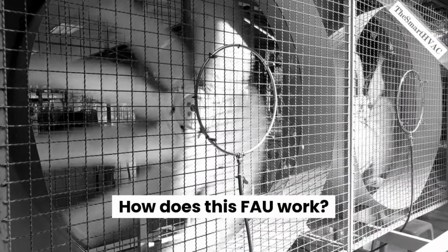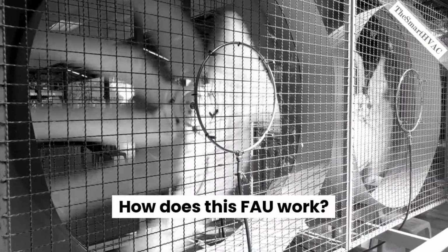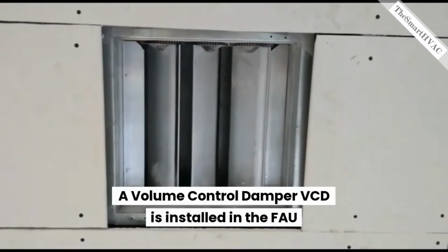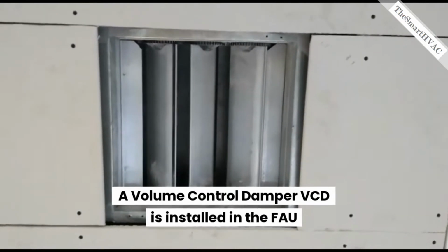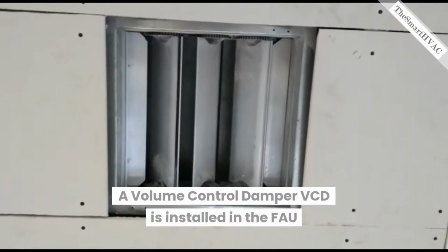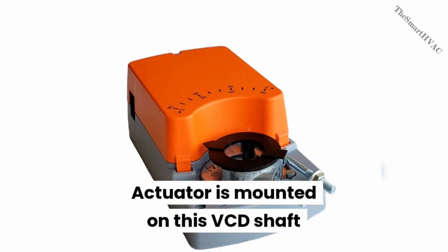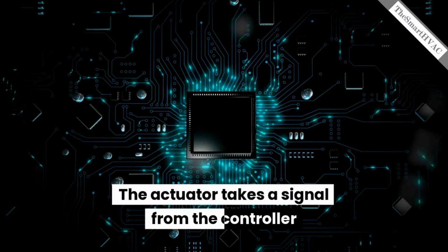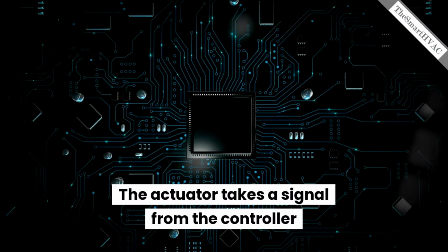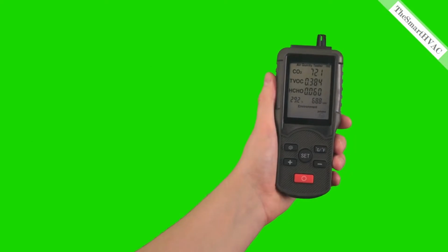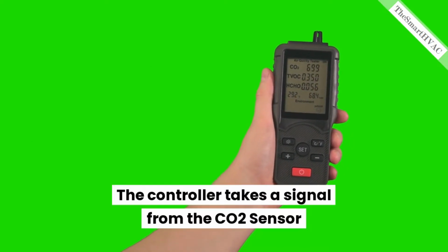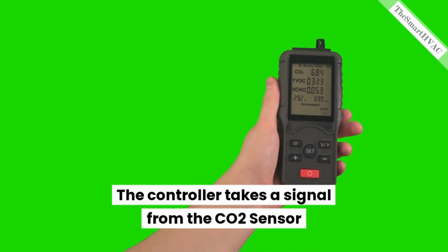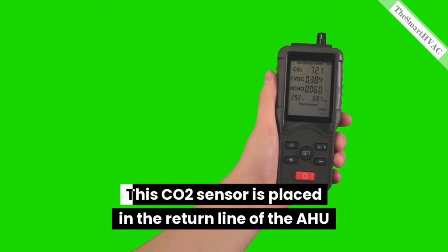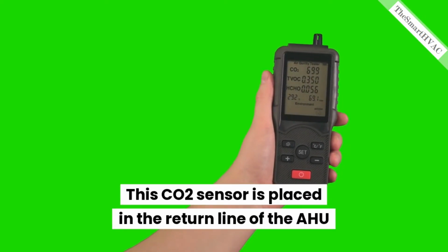How does this FAU work? A Volume Control Damper (VCD) is installed in the FAU. An actuator is mounted on this VCD shaft. The actuator takes a signal from the controller, and the controller takes a signal from the CO2 sensor. This CO2 sensor is placed in the return line of the AHU.